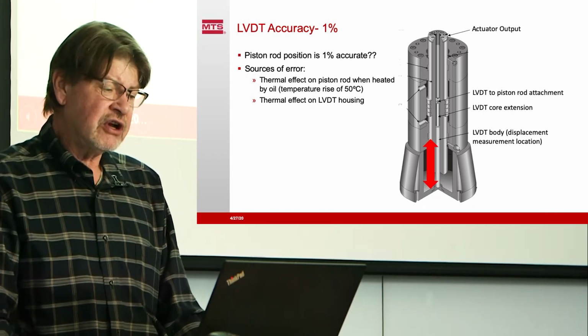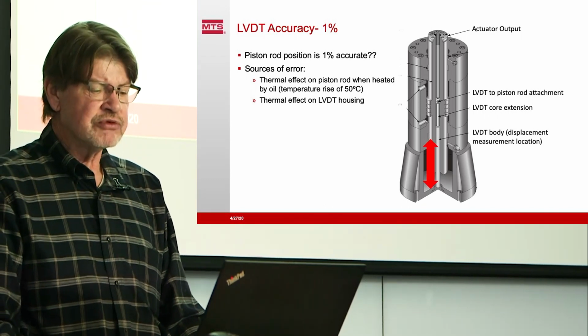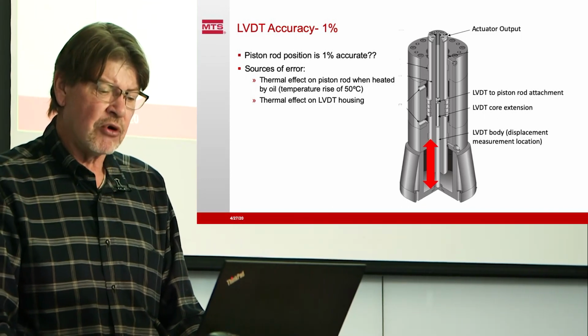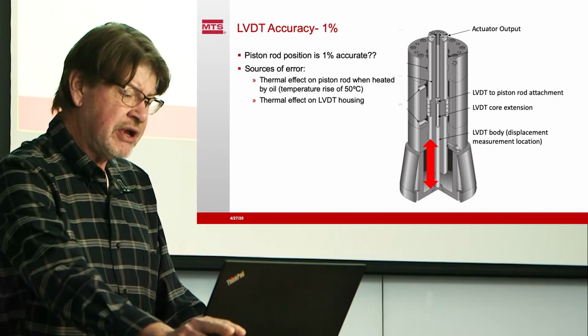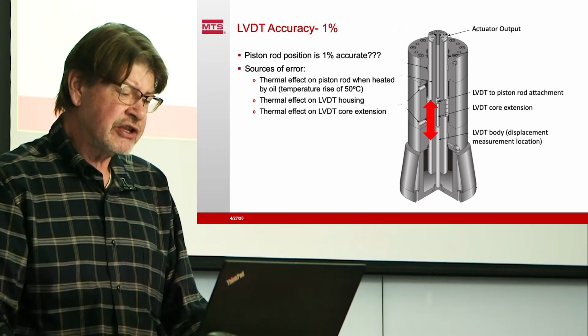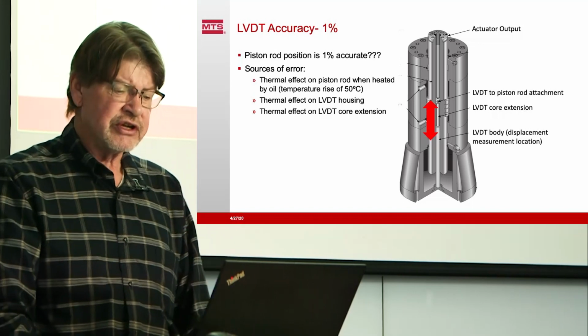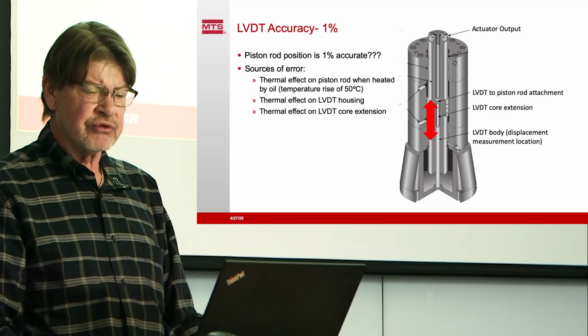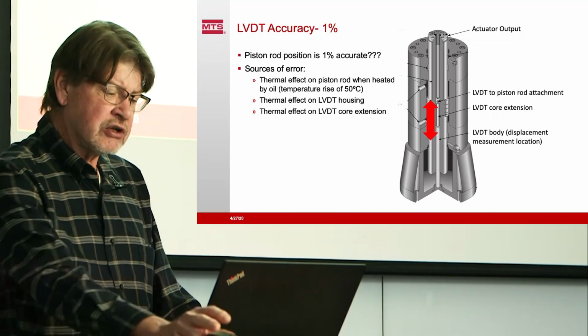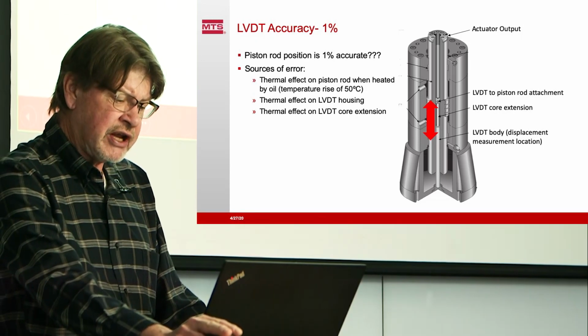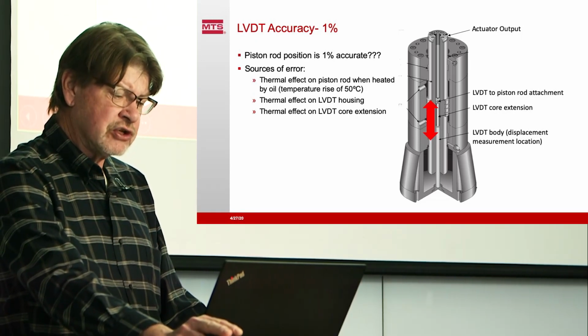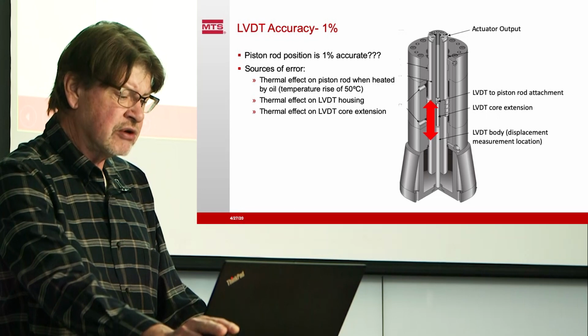The thermal effect on the LVDT housing. As the housing warms up, it's going to get longer. The measurement point is going to move up relative to the base. Thermal effect on the LVDT core extension. The LVDT is attached to the piston with a rod attachment, and then we've got a core extension as shown down here. That has a thermal effect. When it gets warm, it gets longer, and so the end of the piston rod is going to move up.